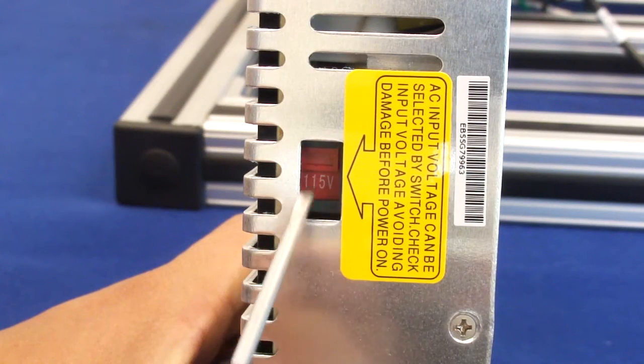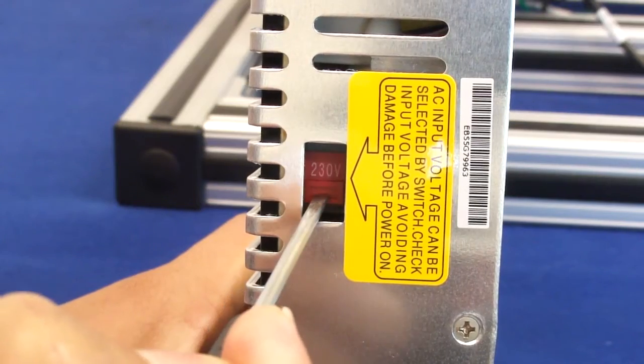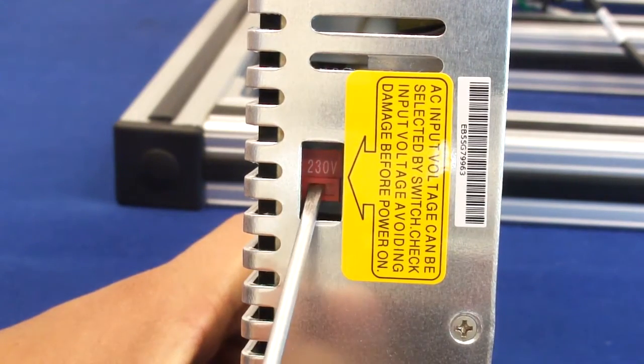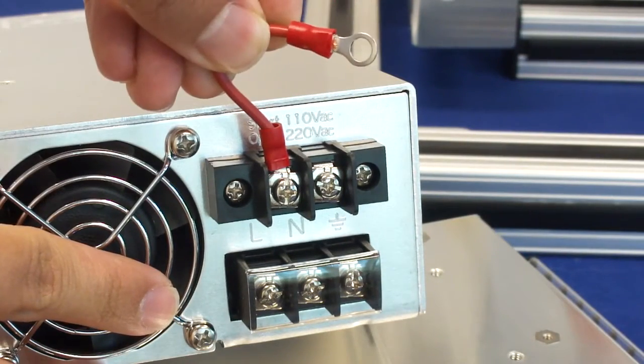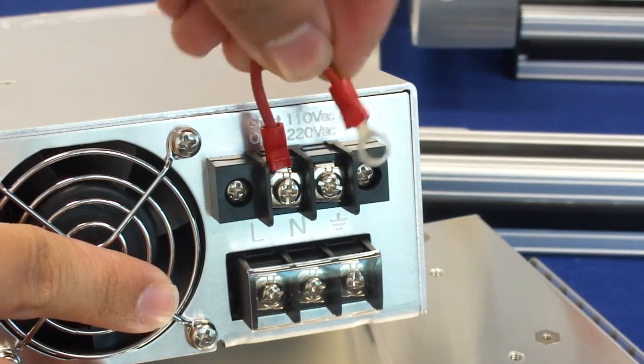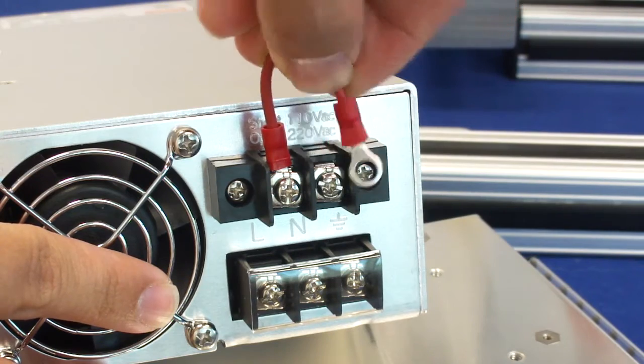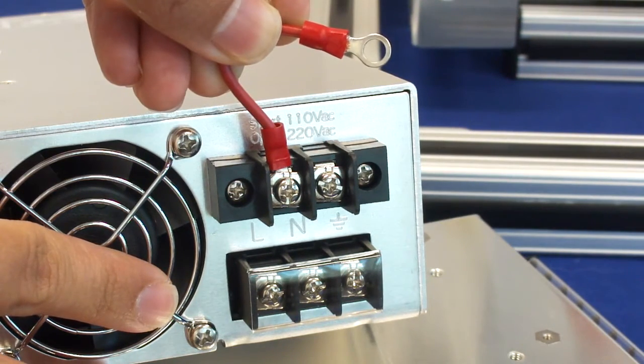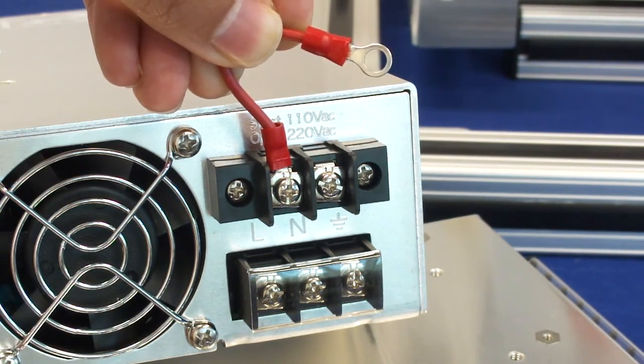Adjust the selector on the DC power supply to match the AC input level. When using the 1kW high capacity power supply, short the selector terminals for 110 volts level and leave the terminals open for 240 volts level.